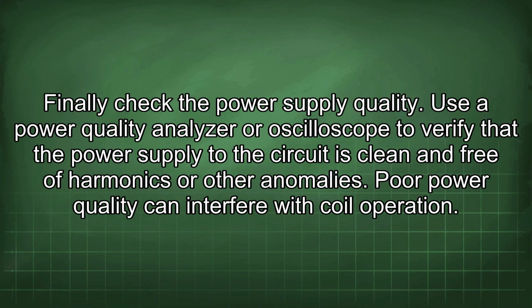Finally, check the power supply quality. Use a power quality analyzer or oscilloscope to verify that the power supply to the circuit is clean and free of harmonics or other anomalies. Poor power quality can interfere with coil operation.